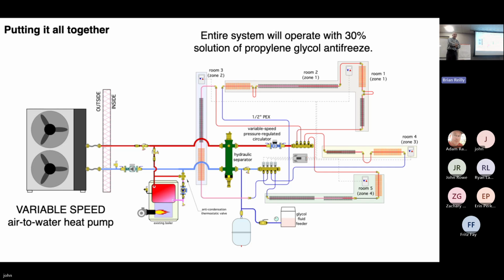Probably the half looks to the water heater. Yeah, so there's all kinds of scenarios like that, but the guiding principle is always put the heat pump where the lowest water temperature is. Domestic water heating is a really good load for a heat pump because many times you're starting with 50-degree water. So if you're heating a tank as a preheat tank with the heat pump and you've got 50, 60-degree water coming into it, you're gonna have really good COPs on it. Heat pump's able to run at relatively low temperatures.